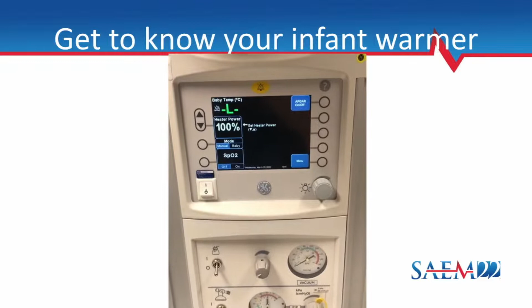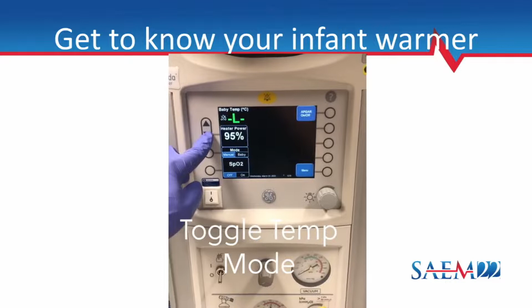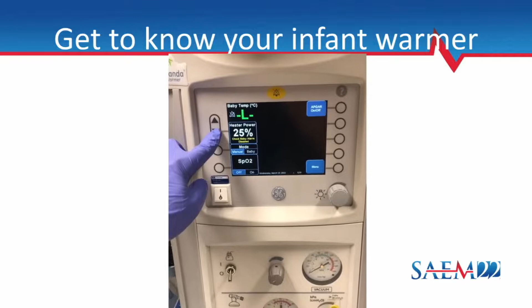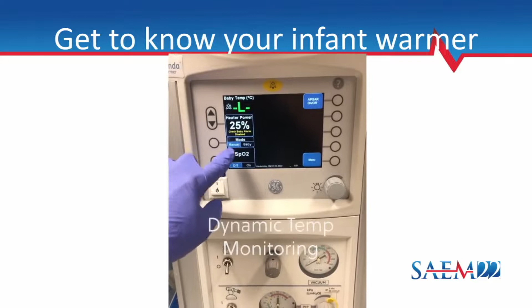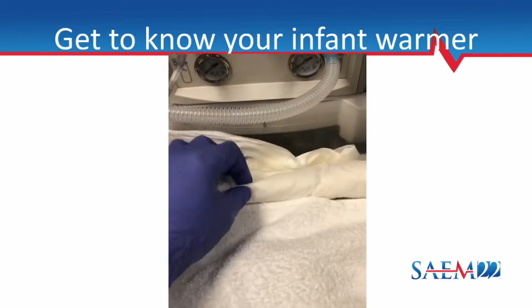But once it gets to this page, you'll hit the Admit Baby button, and it'll bring you to the temperature management screen. Most of the time, you can stick on a manual mode, so just start at 100%, get that baby warm, keep that baby warm. There is a lower limit of 25% power, and it won't go below that. There's also dynamic temperature monitoring, so if you toggle the mode here, you can set a temperature to 36.5 or 37, and attach a temperature probe to the baby's skin, and it'll automatically adjust the power that it's giving to maintain that temperature.